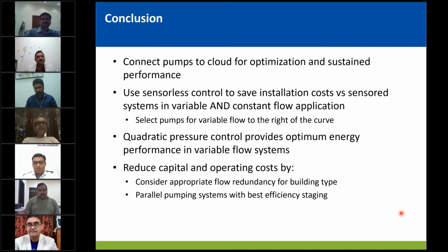So in summary, if you connect pumps to cloud for optimization and sustained performance, you get the most of the performance of the asset. Use sensorless to avoid higher installation costs and the risk associated with the sensor systems. By knowing the flow rate, we can achieve more energy savings, not only for the pumps, but also for the system as a whole. And quadratic pressure control curve saves higher energy and gives more value for money over a period of time.